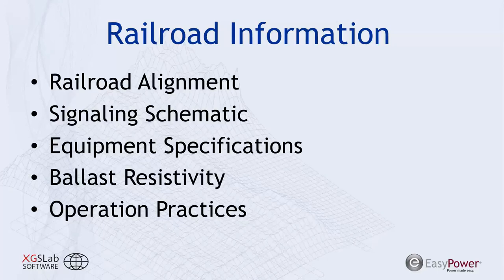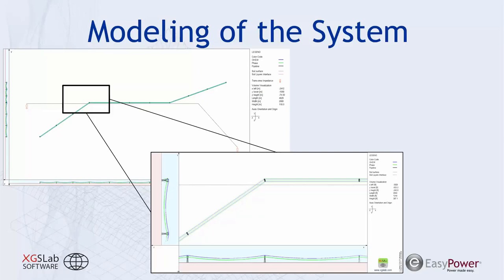And what we end up with is that you have a very complex system with a lot of different pieces from different sources, and it's easiest to evaluate these systems in a software such as XGS-LAB, where you can import from your transmission line design model the DXF into XGS-LAB, and possibly import the pipeline location and geometry from the pipeline design into XGS-LAB, and co-locate those into your modeled environment. You can incorporate the transmission line structures themselves, the shield wires, account for how much induction occurs on the shield wires and how that affects your overall magnetic fields at your pipeline. And this is able to account for very complex systems that have multiple transmission lines, multiple recipients, and multiple operation scenarios to evaluate.